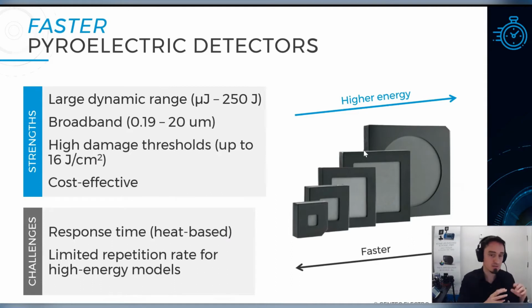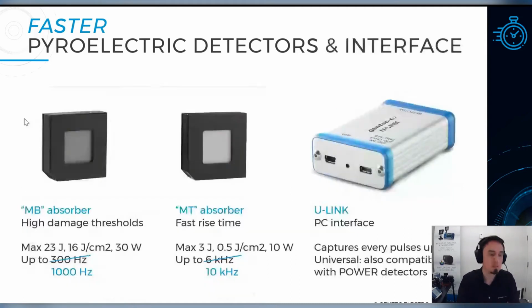You just need to take this detector and plug it into a monitoring interface such as a Maestro, or a P-Link or a U-Link interface to get to your computer. Some of the challenges, once again, the response time is heat-based, so they can be pretty slow, and the repetition rate will typically be in the hundreds of hertz up to 1 kilohertz. So we spent a lot of effort to release new electronics and new crystals and a way to assemble those detectors, mainly for the QE12 and the QE25 detectors, so 12 millimeter and 25 millimeter square detectors.